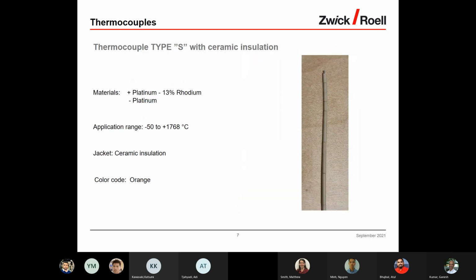Next one, thermocouple S with ceramic insulation. Also the material is, on the plus side, platinum and 13% rhodium, on the minus side, platinum. Application range from -50 to +1768 degrees Celsius. Here the jacket is ceramic insulation, and the color code is orange.